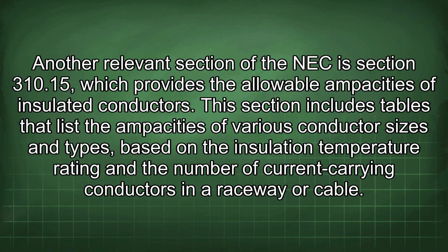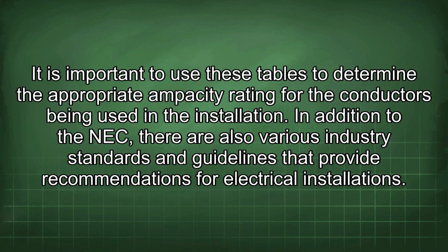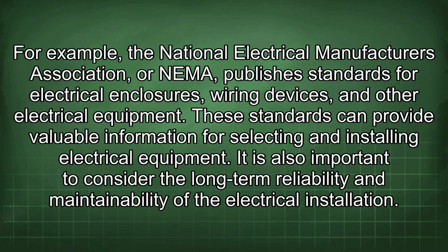Another relevant section of the NEC is Section 310.15, which provides the allowable ampacities of insulated conductors. This section includes tables that list the ampacities of various conductor sizes and types, based on the insulation temperature rating and the number of current carrying conductors in a raceway or cable. It is important to use these tables to determine the appropriate ampacity rating for the conductors being used in the installation. In addition to the NEC, there are also various industry standards and guidelines that provide recommendations for electrical installations. For example, the National Electrical Manufacturers Association, or NEMA, publishes standards for electrical enclosures, wiring devices, and other electrical equipment. These standards can provide valuable information for selecting and installing electrical equipment.